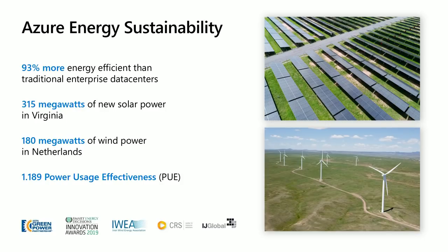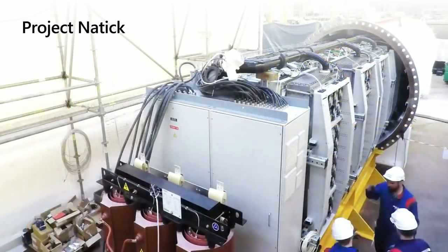And then we're also focused on PUE, improving the efficiency of our data centers. And that's been continuously going down as we build out new data center designs. Every data center gets more and more efficient. If you take a look at the average PUE across all our data center footprints, of more than 100 of them over the last 12 months, we have a PUE of 1.189. And that doesn't reflect the state of the art, where the data centers that we're building out right now have a PUE of 1.16. So we're always trying to innovate, though, and make our data centers even better.